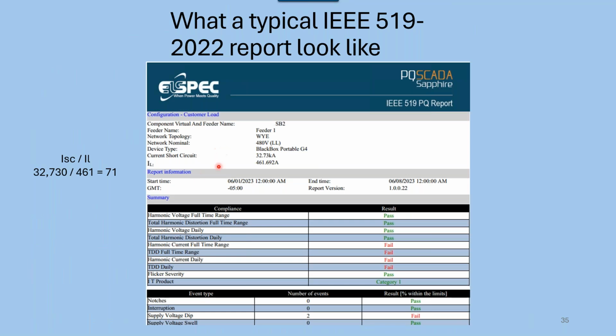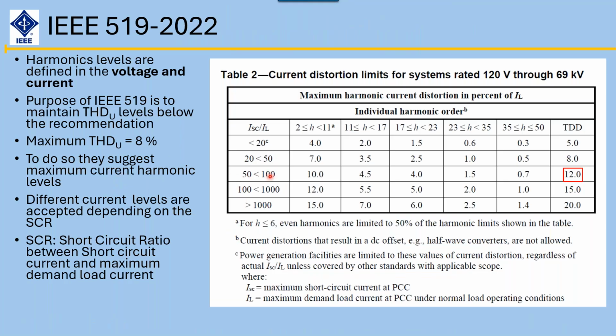Okay? John, you can also, with Elspec, they have products that allow you to have quick recovery of voltage dips and things to help you have an overall stiffer system. Yes, that's for voltage dips. But this kind of report that I'm doing here, I need to look at not just a momentary, but more continuous. So in this case, my short circuit current, which I had to manually put in from our analysis of the single line, was 32,000 amps. The full load current the system calculated was 460. That gave me a number of 71. And if I go back to my 50 to 100, that's 71, which is a fairly stiff system. I got a TDD of 12, and that's what I'll use in my report.